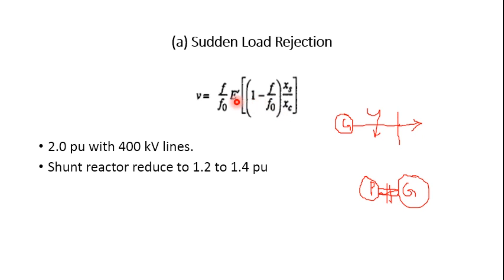E' is the generator voltage before the over-speeding of the prime mover and load rejection. f is the instantaneous increase in frequency, and f₀ is the normal system frequency. This increase in voltage may go as high as two times the rated value if the system voltage is around 400 kV.